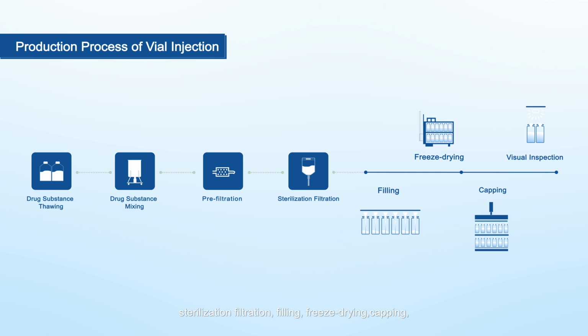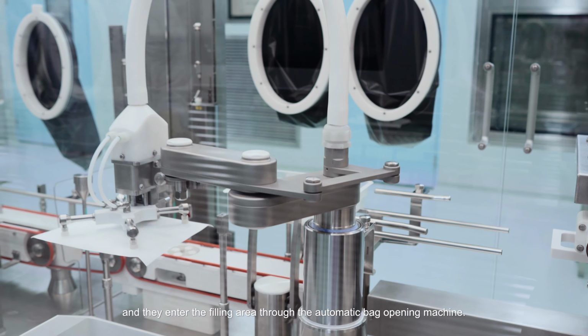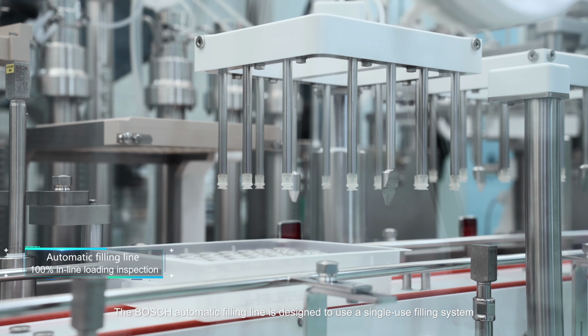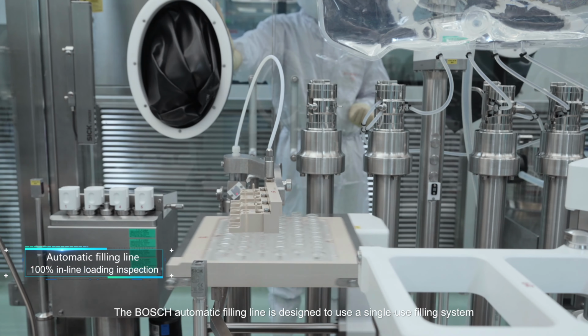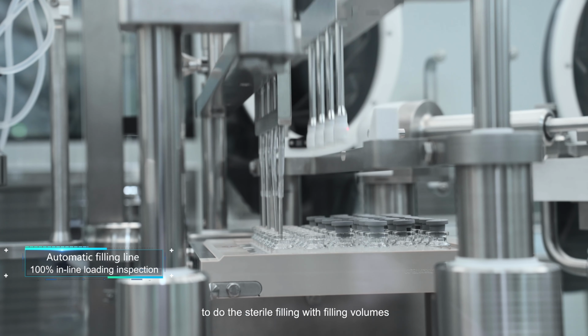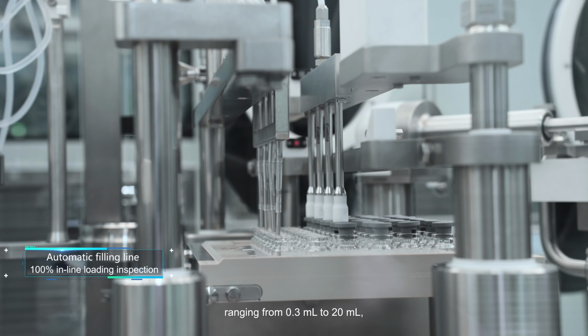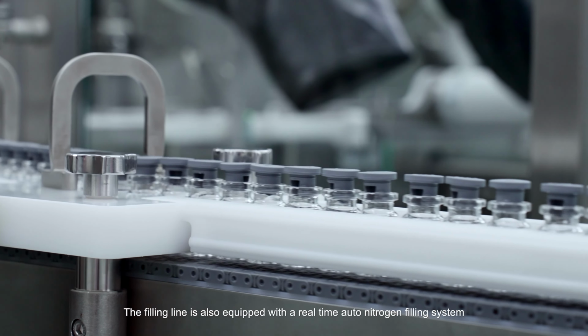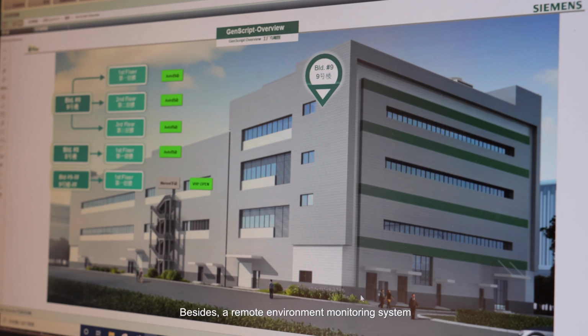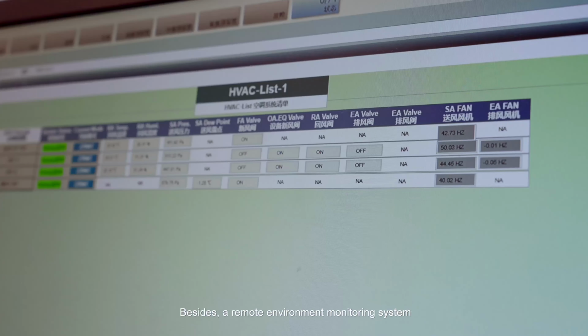Ready-to-use vials and pre-filled syringes are used in the production, and they enter the filling area through the automatic bag opening machine. The Bosch automatic filling line is designed to use a single-use filling system to do the sterile filling with filling volumes ranging from 0.3 milliliters to 20 milliliters, and high-precision filling is achieved by automatic adjustment of the filling pump parameters. The filling line is also equipped with a real-time auto nitrogen filling system to protect the products with nitrogen while filling. Besides, a remote environment monitoring system is installed to monitor the critical production areas to ensure the working environment meets the GMP criteria.